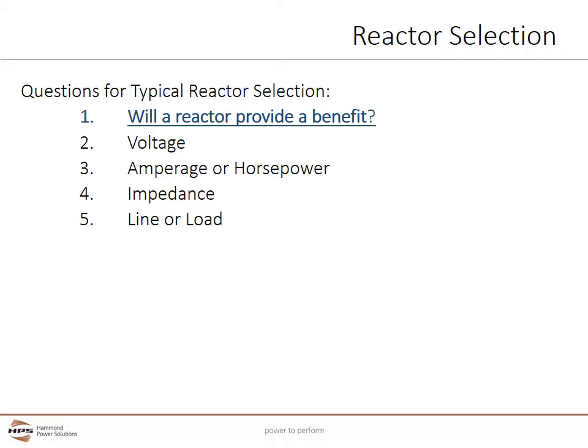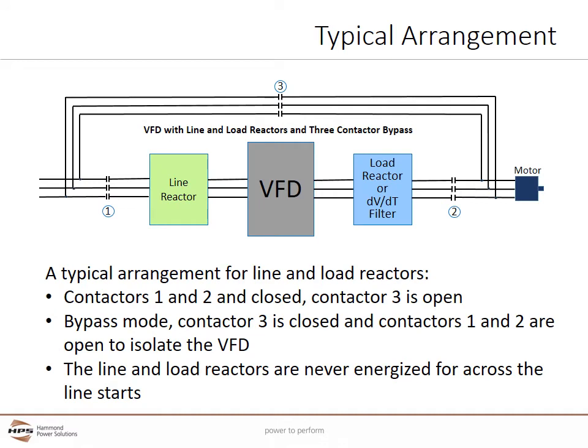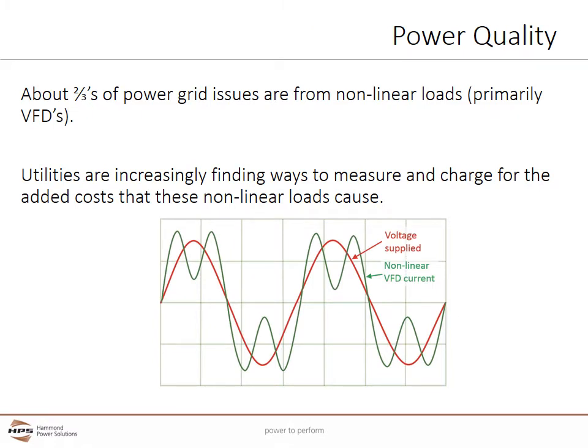Let's start with will a reactor provide a benefit. This diagram represents a typical VFD with an arrangement for both line and load reactors, also wired in what is called a classic 3-contactor bypass arrangement. When contactors 1 and 2 are closed and contactor 3 is open, the drive can run. In bypass mode, contactor 3 is closed and contactors 1 and 2 are open to isolate the VFD. Anything that rectifies AC to DC power is a non-linear load and produces current harmonics. The line side of a VFD is basically a DC power supply and is a classic 3-phase non-linear load.